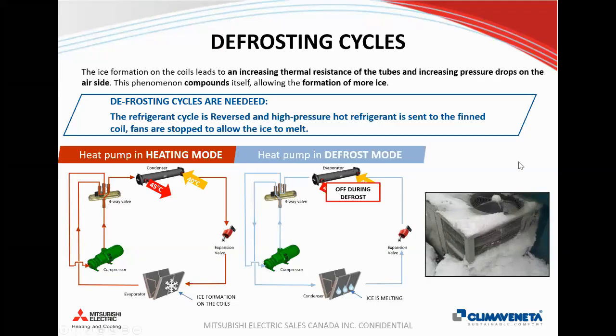So if you do have instances where there's a harsh winter and harsh conditions on a particular day with fixed timers, you might not melt all the ice off the coil. So then it just basically says, okay, well, the next time I'm going to try to do that again. And usually with fixed timers and harsh conditions, it can lead to buildup until eventually someone's going to get a service call about it because the heat pump's not running.